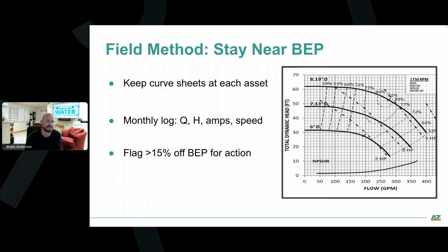For example, one of those systems that I showed you on the map previously, when we took over, they had a well that had been offline for a number of years. They were just cycling it manually to keep it going, but they didn't actually use it in production because it was using so much power. How it was set up was there's a 15 horsepower submersible pump downhole that pumped up into a 7.5 horsepower booster pump, and then that pushed it out to the system.